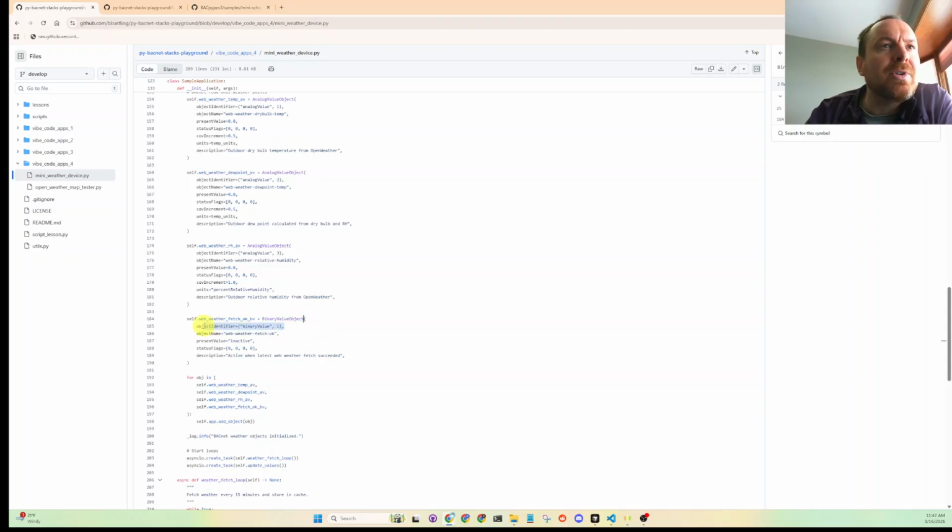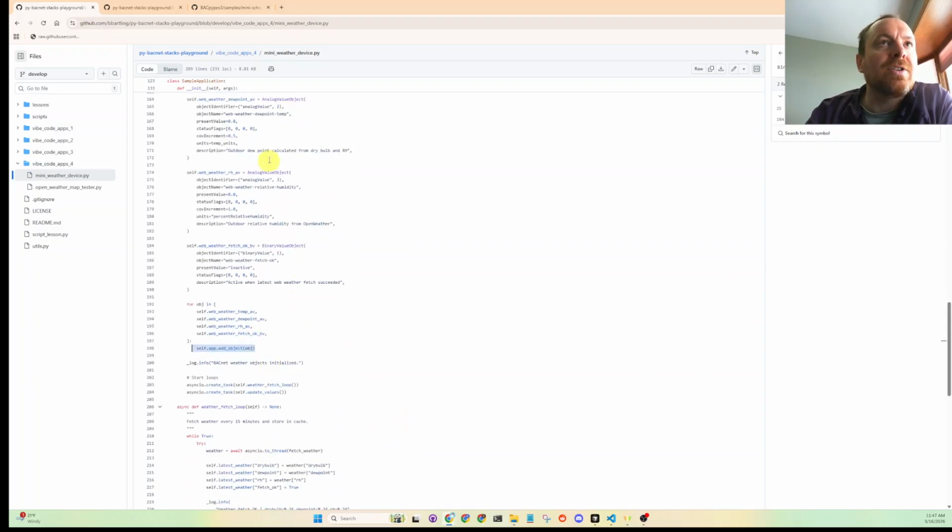The hardest thing to remember is that when you're creating a server, you have to manually increment your BACnet analog values. So this is analog value 2, analog value 1, 3, binary value. We never got into any commandable points, but just remember you have to increment here, because when you add your objects to the BACnet server application, it will error if you don't increment those.